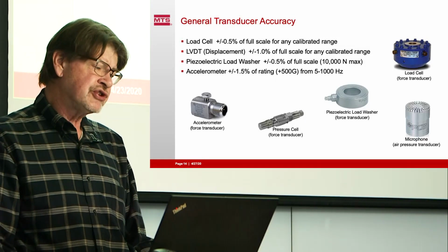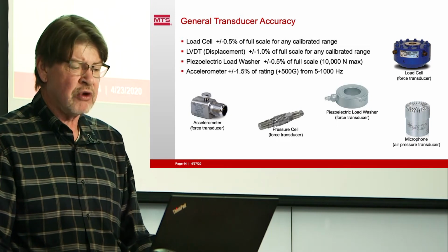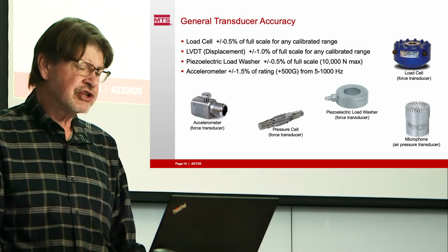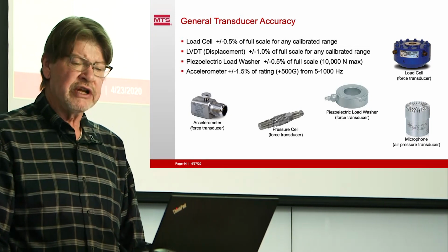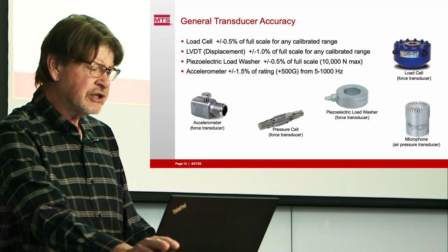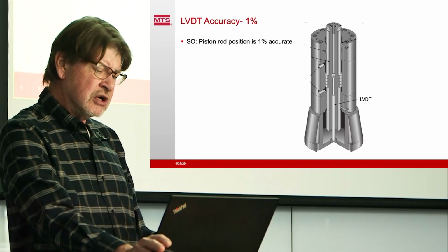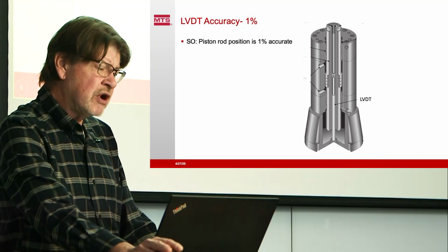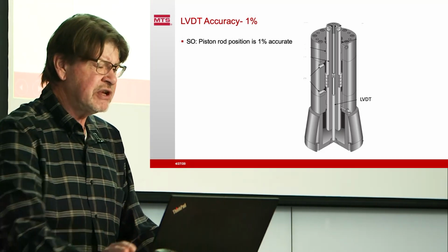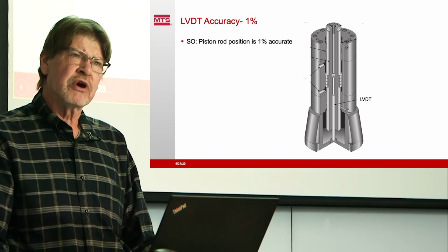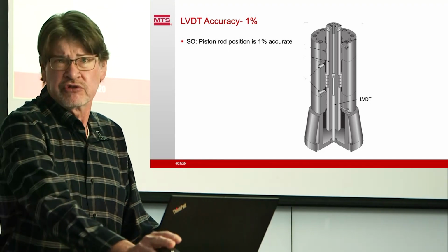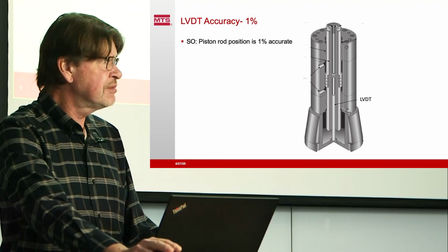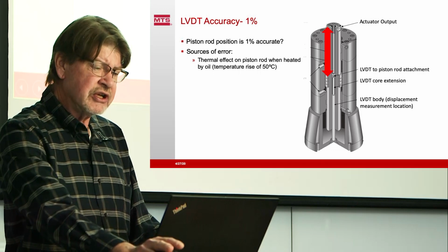We look here at a load cell at 0.5%, an LVDT is 1%. Load washers, accelerometers all have a so-called rated accuracy. Well, let's take a look at that rated accuracy a little bit. We look at an LVDT here, it's 1% accurate. Well, that must mean that the piston rod is correct to 1%, right? I mean, if the transducer is right to 1%, the piston rod should be to 1%. So let's take a look at that.